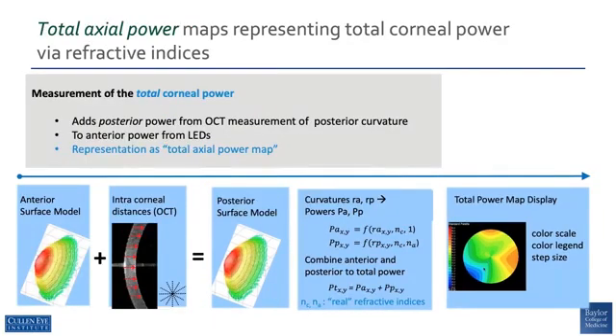To get total axial power representing total corneal power with refractive indices, we add the posterior corneal power from the OCT measurement of the posterior curvature to the anterior power from the LEDs, and that becomes a total axial power map. The swept-source OCT measures the intracorneal distances and undergoes a modeling and calculation to get a total power map display.